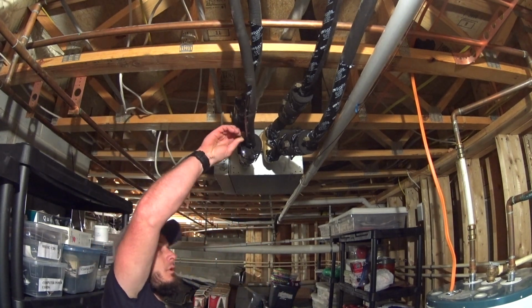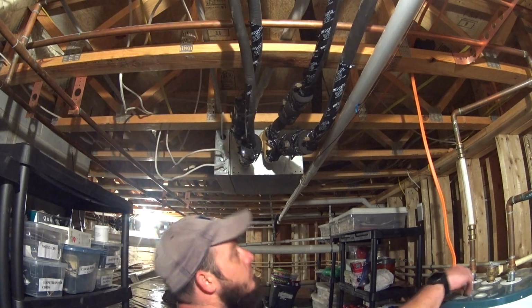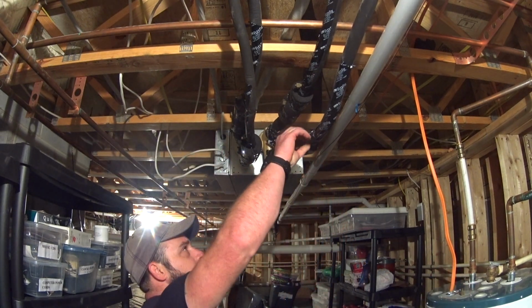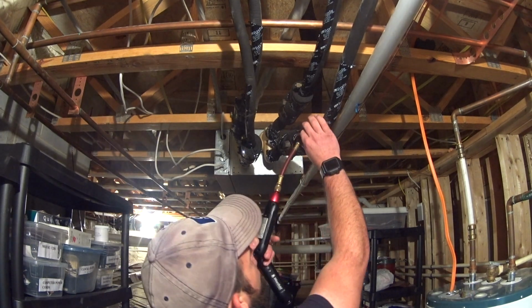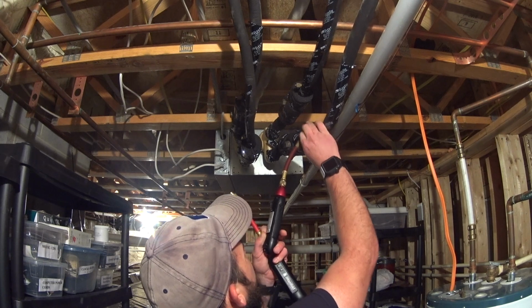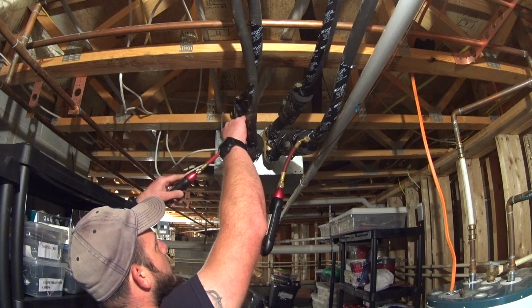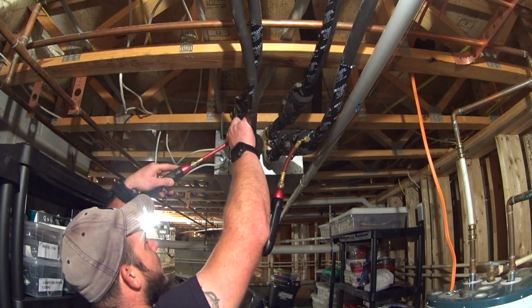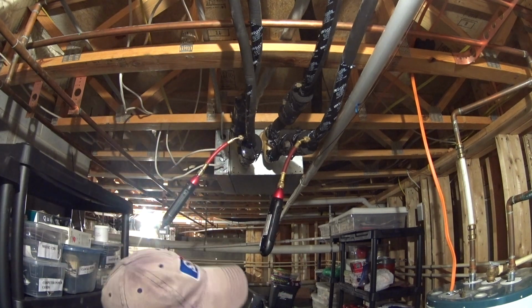I'm going to put a pressure probe on each circuit and then isolate the valves and just use the pressure test that came from the condenser. Obviously I lost a couple of PSI there, maybe, and then there's a potential that I lost a couple of PSI there as well.